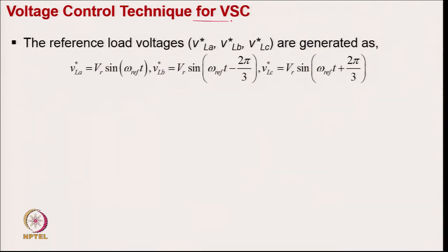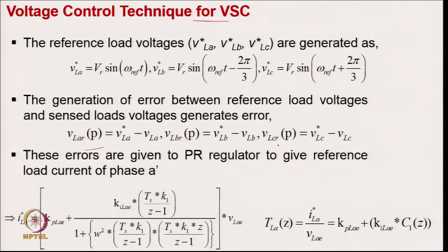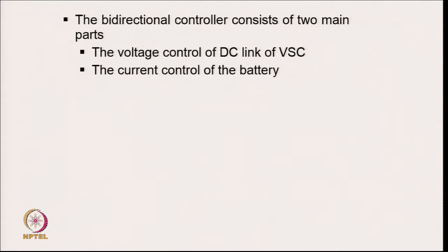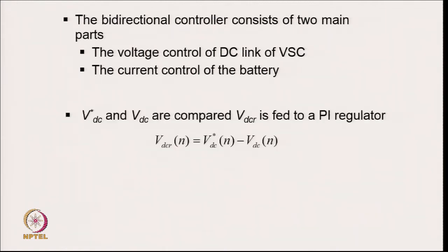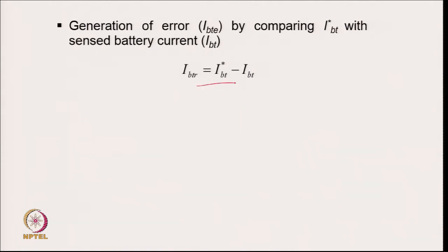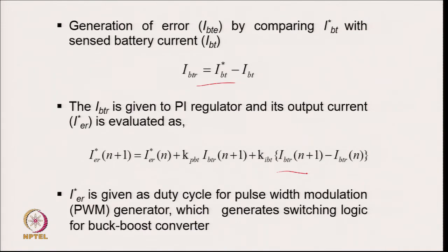This is in islanding/voltage control mode: we have three-phase reference voltage, voltage error, and pass it to calculate reference load current for all three phases. For bi-directional current control, we have the DC link voltage, sense the DC link voltage, pass through a low-pass filter so only the DC component remains, use a PI controller to give battery reference current, sense battery current, and again use PI control. The output is compared with a sawtooth signal to generate gating signals for the two devices of the bi-directional buck-boost converter. The bi-directional control has two main parts: voltage control of DC link voltage and current control of the battery.